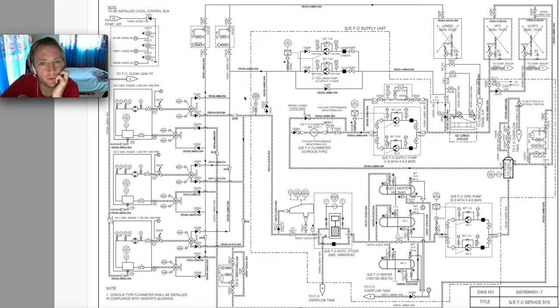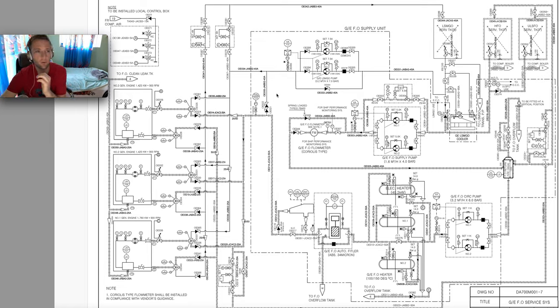The only thing that was difficult during a blackout was that we need to start one of these pumps manually. So in the event of a blackout you do not have much time to wait to circulate — you make it direct. But if you have time, you will try as much as possible to cool down your generator. If you like to make a changeover, the diesel is already waiting there, not yet started.